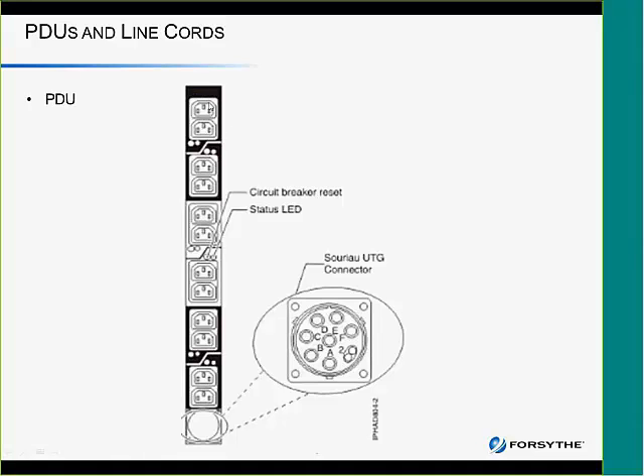This is actually what the PDU looks like. So these are each 10 amps. And these are each 10 amps with the circuit breaker. Interestingly enough, I have actually had servers go down because people actually plugged the server into the first socket, then a new I/O drawer came in and they plugged it into the second one, and everything was going fine until the server got really busy, and what happened was it started to pull enough amps to trip the circuit breaker, and that took everything down.